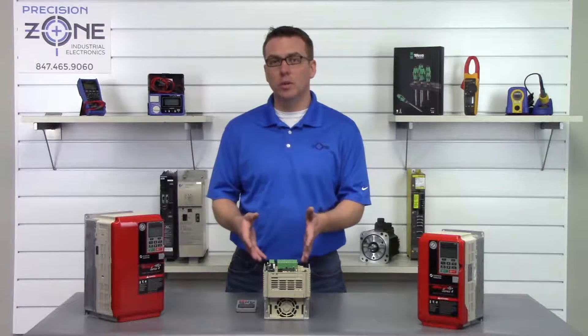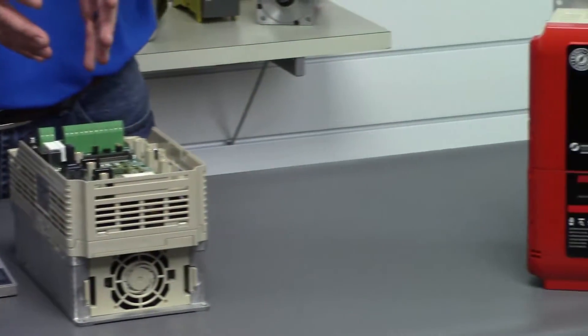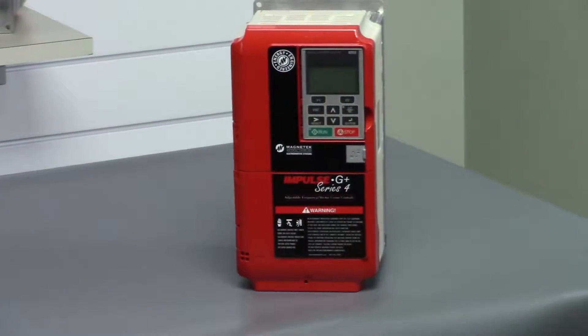Low insulation on the motor or the motor cables will cause an overcurrent alarm, and you'll want to use a megohmmeter to verify the integrity of the insulation to ground.